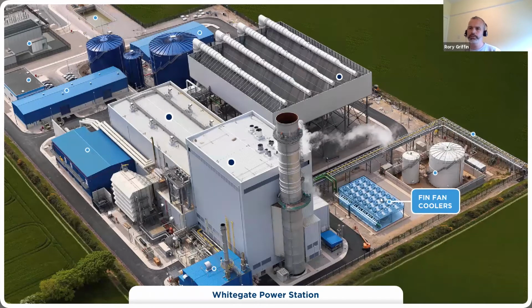On the center lines, for example, there's 8 bearings in the machine with lube oil on them. A lot of heat is extracted through the lube oil. So triple CW system, we call it, is the closed cooling water system. This is the cooling for the cooling water. This circulates around the site, extracting heat where required.